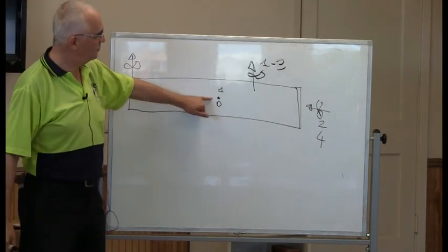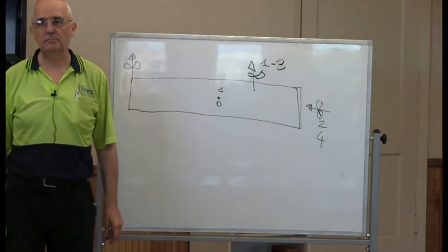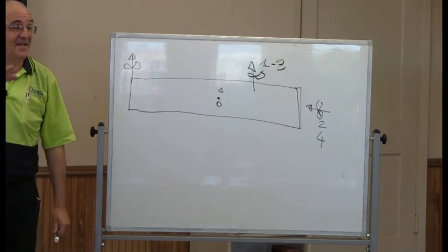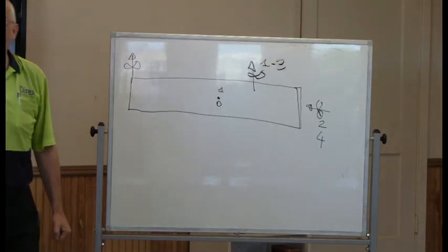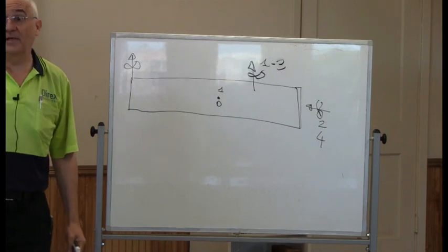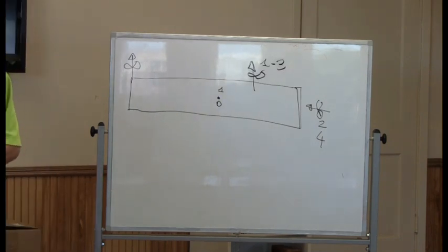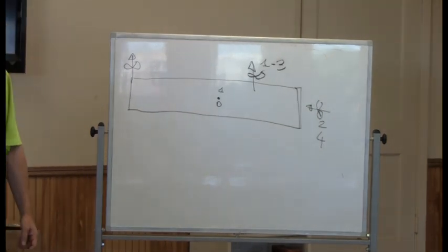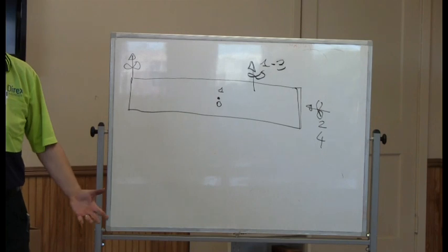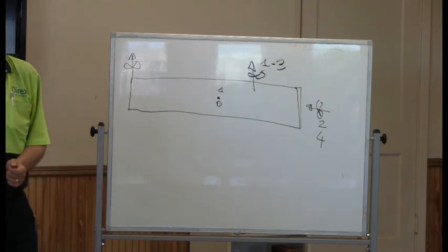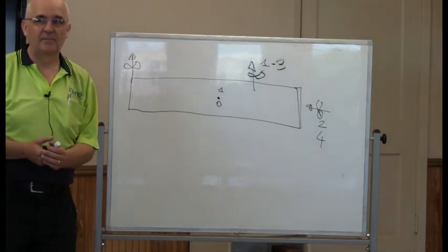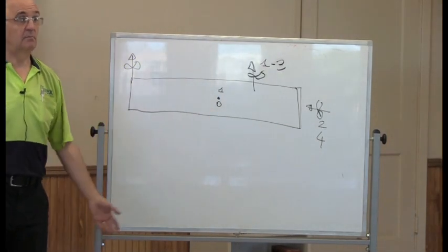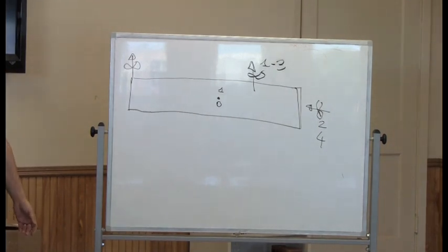Okay, and actually, we had some pretty simple checks. And see where the flame goes. Yeah, and you were making sure that you were not backdrafting. Yep. But when you saw your flame going one way or another, it was not telling you exactly what you were doing. Just that you were not on the wrong side of the fence, but not how far from the fence you were. Food for thought?